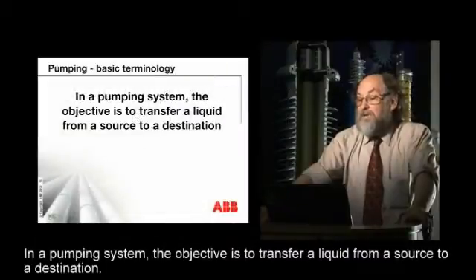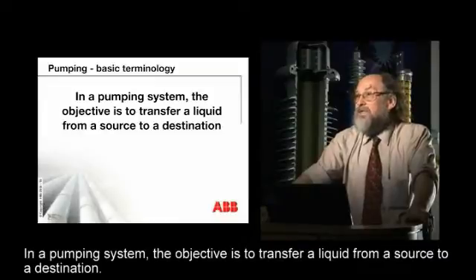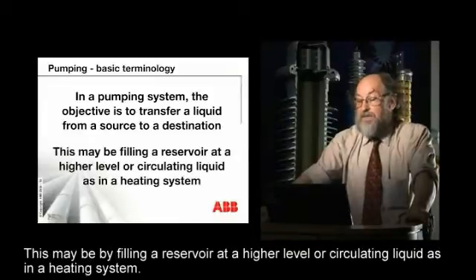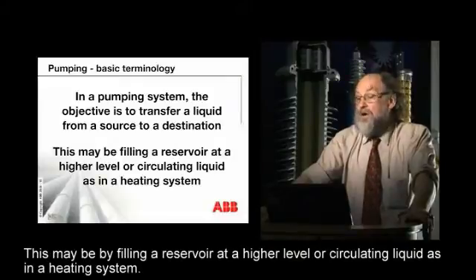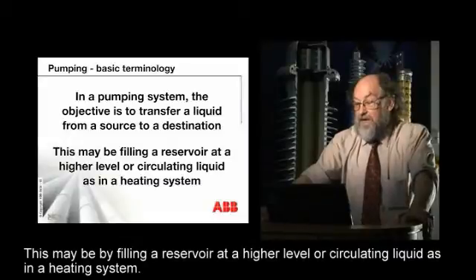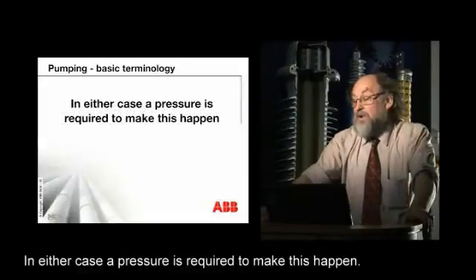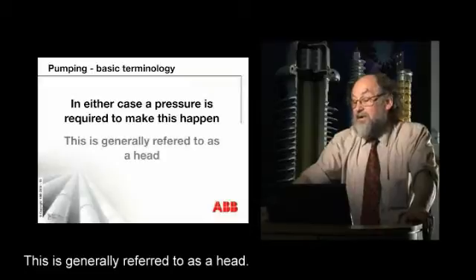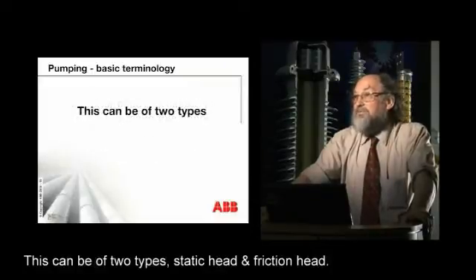In a pumping system, the objective is to transfer a liquid from a source to a destination. This may be by filling a reservoir at a higher level or circulating liquid, as in a heating system. In either case, a pressure is required to make this happen. This is generally referred to as a head. This can be of two types: the static head and the friction head.